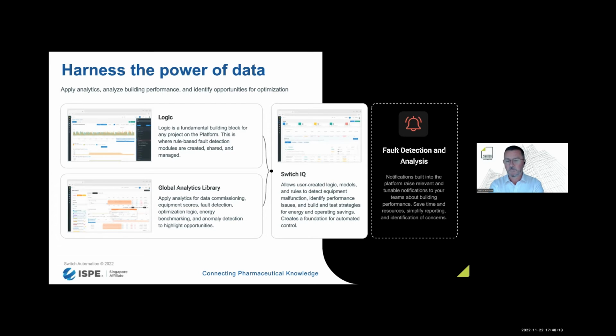You can see that the filter on that valve is possibly choking up, or maybe the actuator is failing. So you're getting insight and alerts into these things in advance of an actual failure. You're not waiting until your temperature is no longer met, you're able to address the issue in advance, which means less downtime for the systems and better satisfaction from operators and occupants, because they're not having to complain that things are not working.